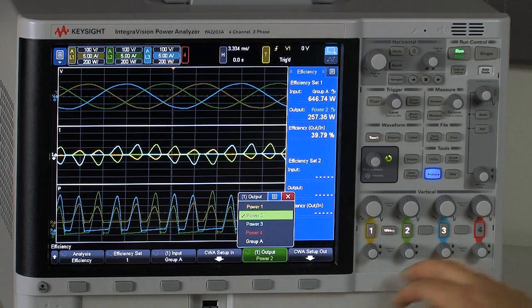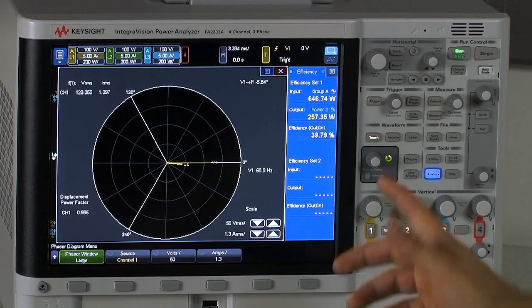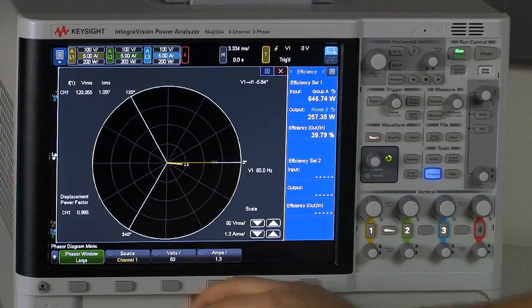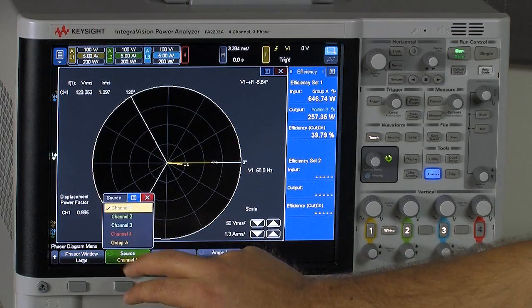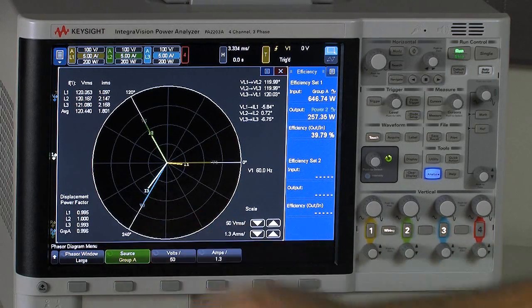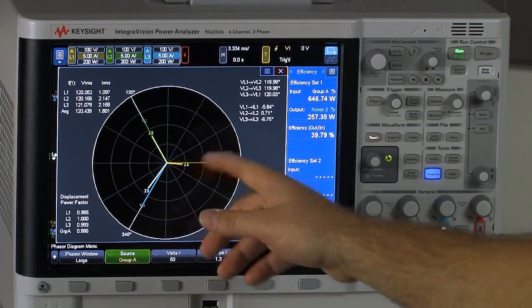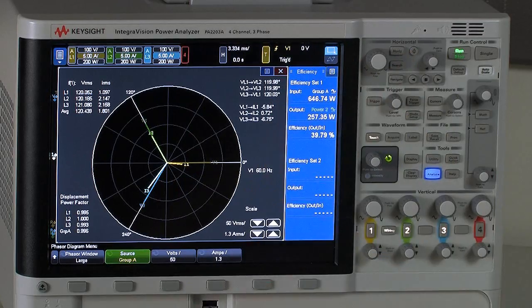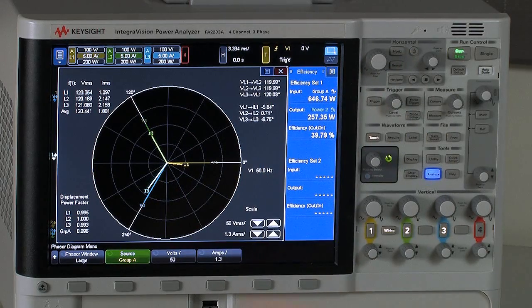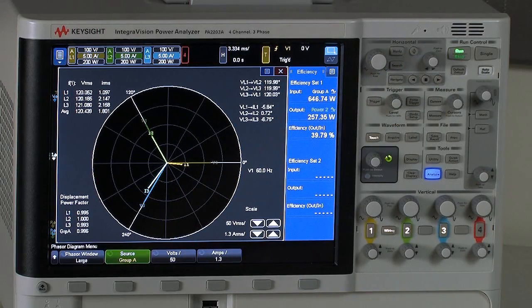And then I think finally, another very important feature would again be our phasor diagram feature where again I choose the source, I go to group A, it brings it up, we can see we sort of have the three phases, the currents are in pretty close alignment here, but again all I have to do is select that group measurement and my phasor diagram is ready to go.